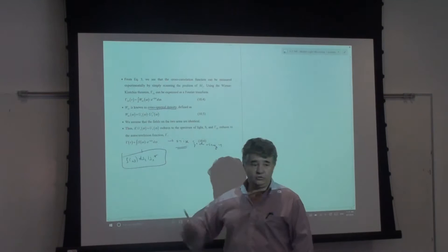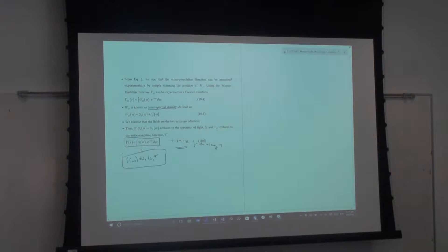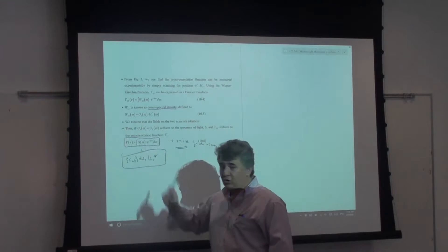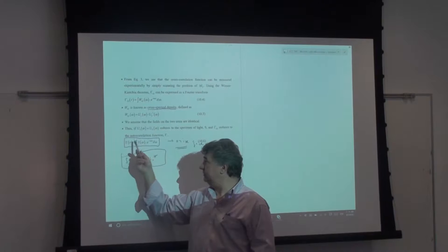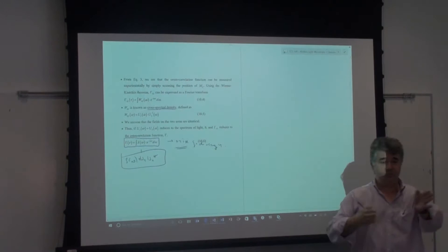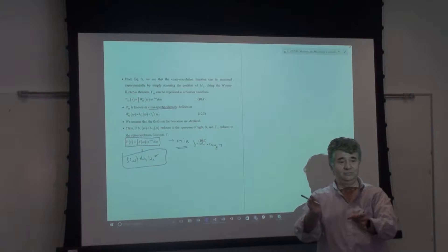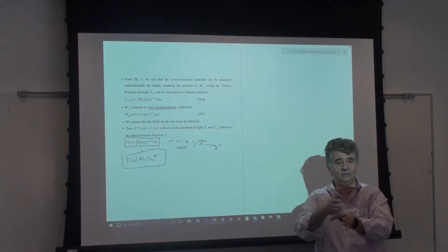The autocorrelation function contains all the spectral information — you can choose to measure the optical spectrum in the time domain rather than with a prism or grating. With a grating spectrometer you spread colors by angle versus wavelength. With FTIR you scan a mirror and record interference as a function of mirror position, then numerically Fourier transform the signal to get the spectrum.